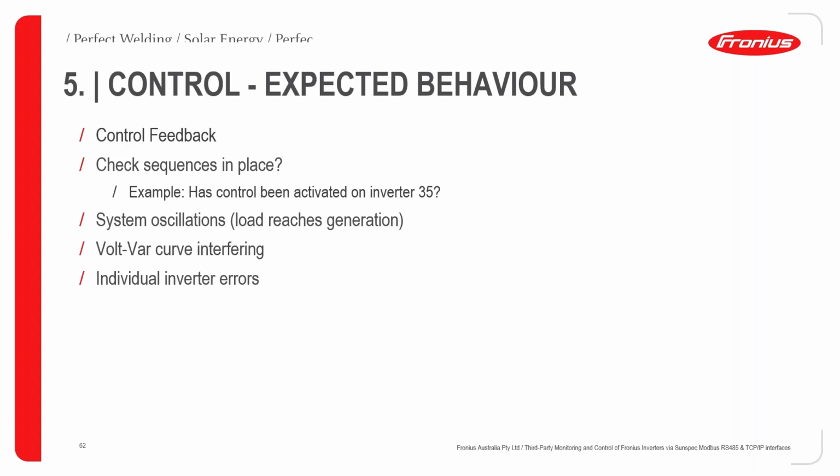Some situation that can occur is oscillations. This can happen with typically bigger generation whenever load can match it. So how will you handle it? Because I've seen responses thinking it's actually the control not responding properly. Is it, or is the load control feedback in a way not implemented properly? Maybe a little more thought needs to be put into that.